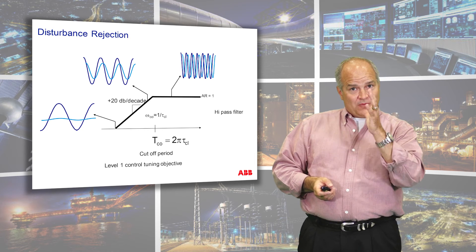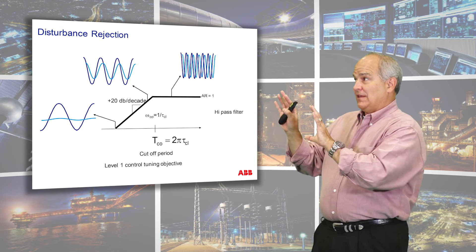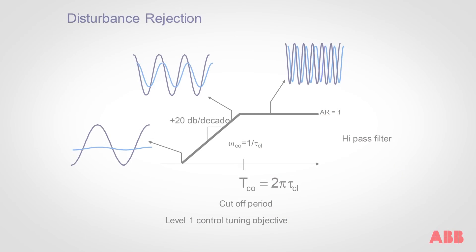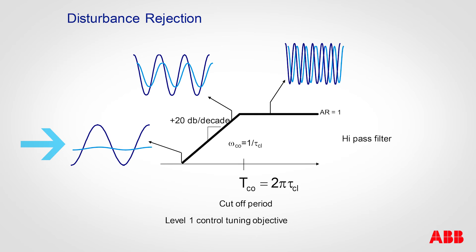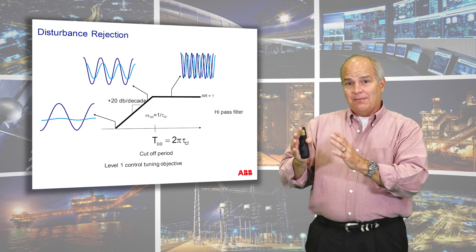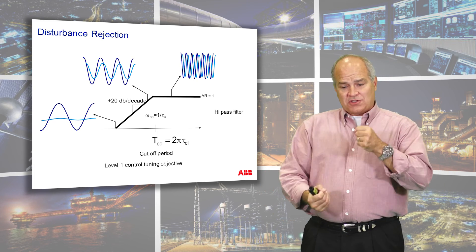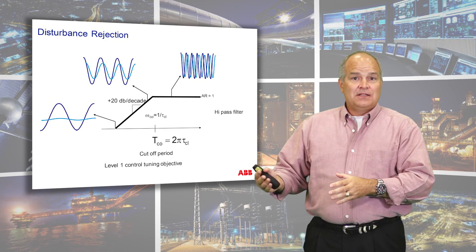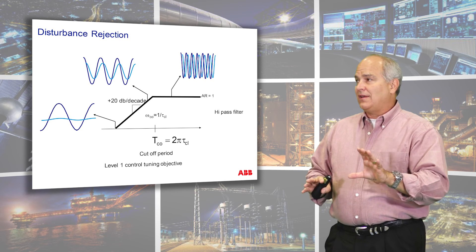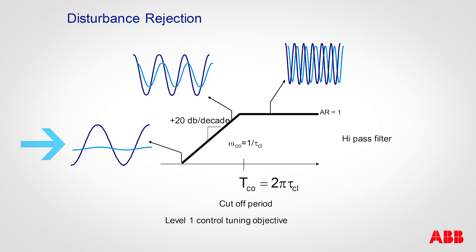Notice the picture I showed before — it was a mirror image. As we change the set point slow, my control can keep up. But as I change faster and faster, my control can't keep up. It's exactly the opposite when you look at disturbances: if my disturbance is very, very slow compared to how it's tuned, I can redirect that energy into my actuation device and my process looks fine. Now you have to make some decisions about how much of that energy you want to go into the actuation device versus the process. As your actuation device absorbs more and more, it's like a shock absorber on a car — if it's wiggling all the time, eventually it's going to wear out and you get into maintenance issues. These are some equations we talked about with cutoff period and closed loop time constant.